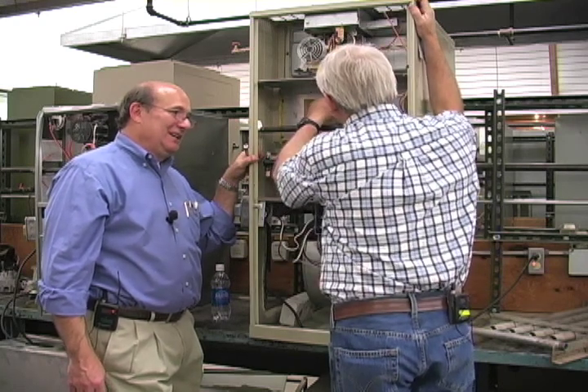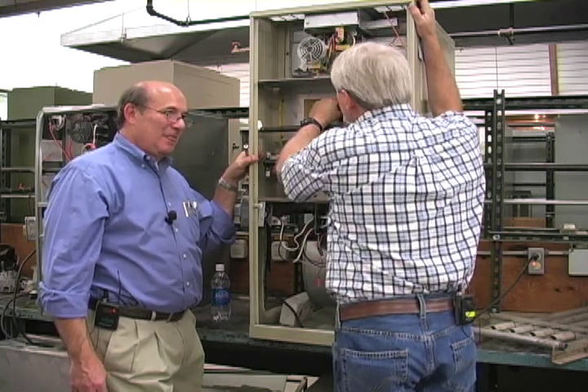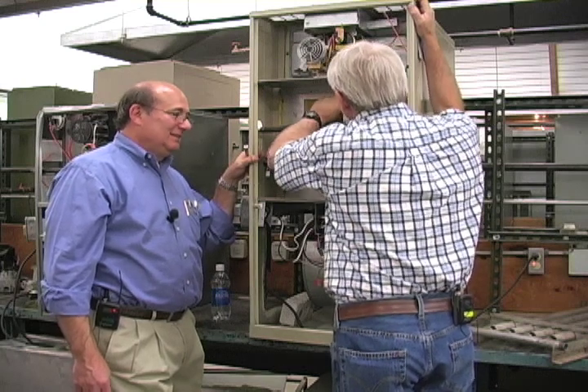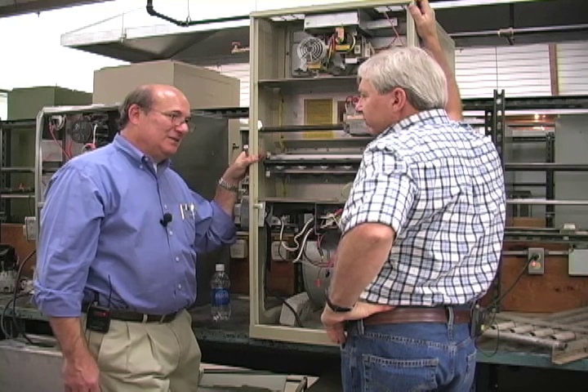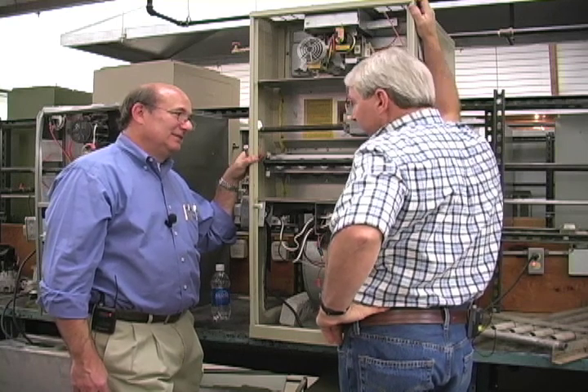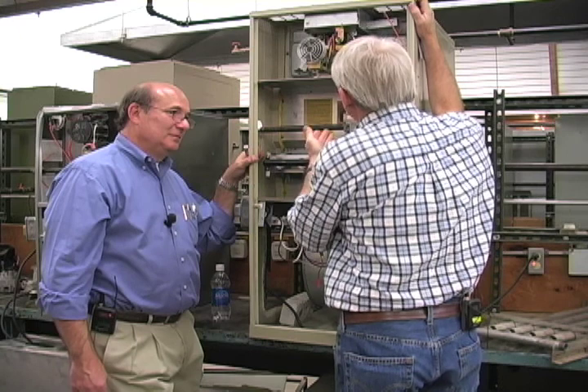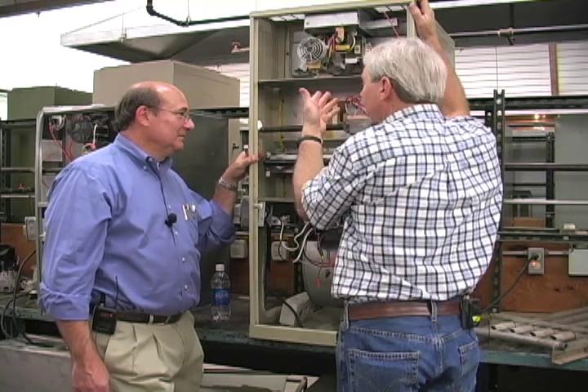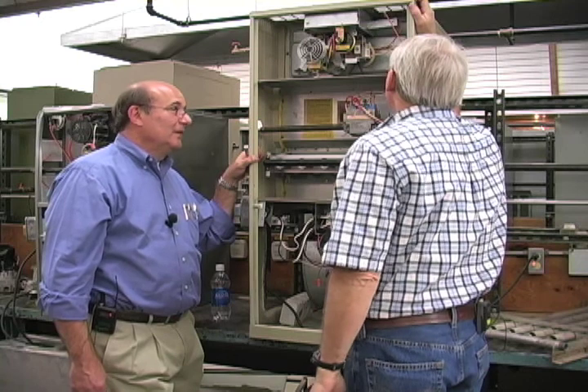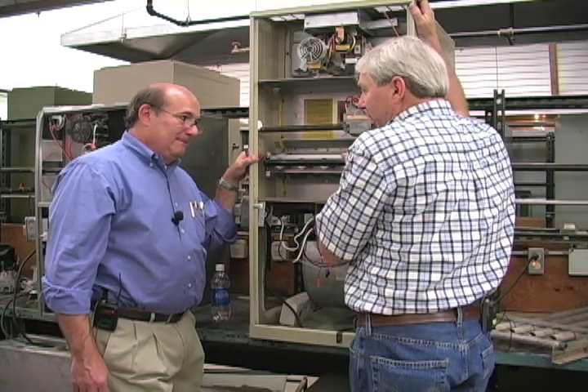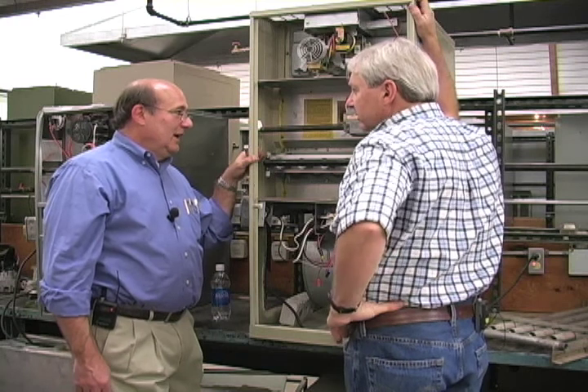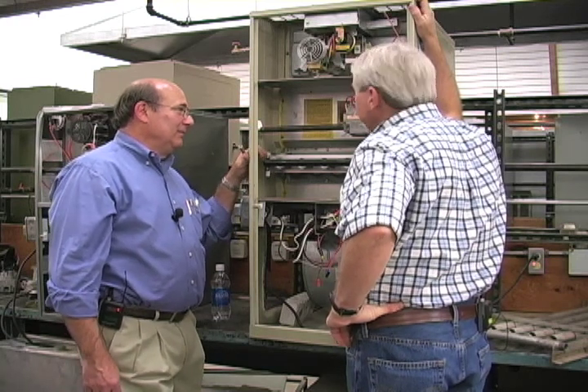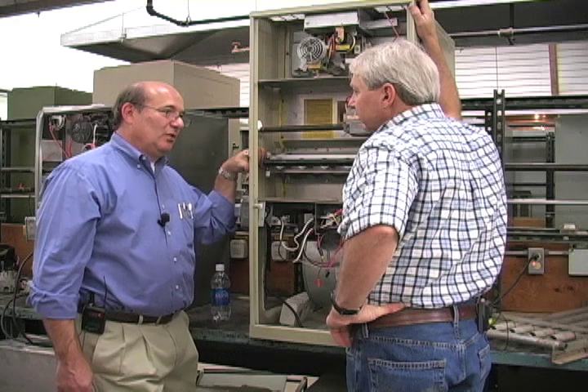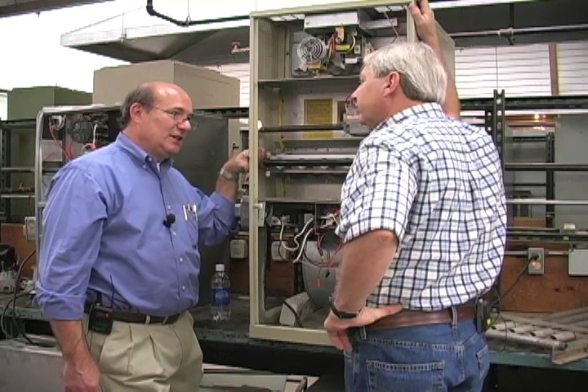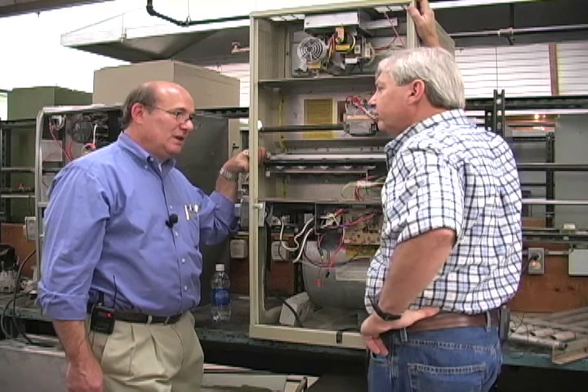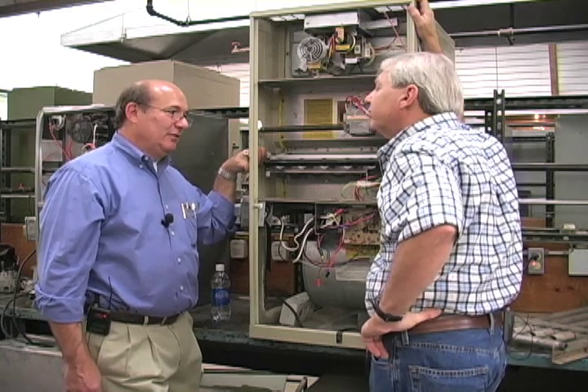There's a lot of things that you could run into if you want to do a safety check on a system, like on a boiler, or maybe a bad blow down valve. That's probably the kind of thing that inspectors are not going to do. So I guess if they're looking in here, should they look for crystallized insulation or corrosion, and maybe be recommending an annual service? Yeah, those might be indications, but moreover, in these types of controls, I'd look for burnt wires. Okay. I'd look for insulation that's cracked or looks like it's charred, or some high temperature failure of a system.